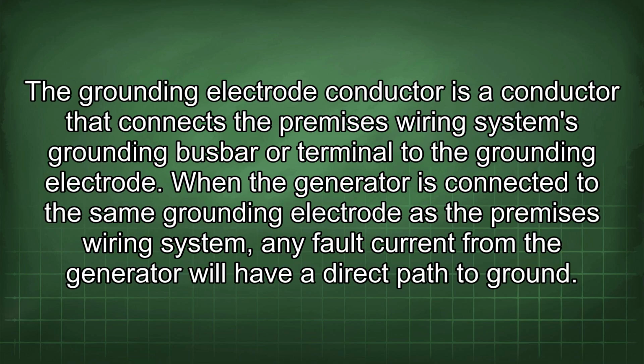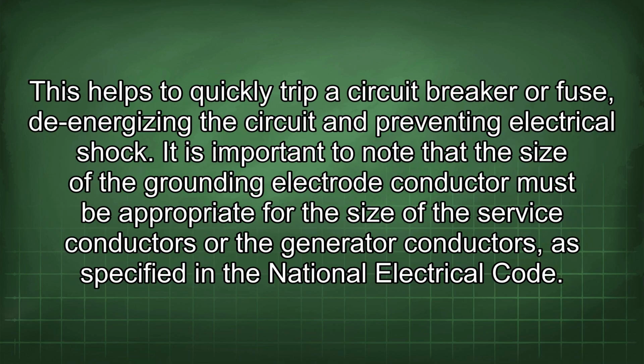The grounding electrode conductor is a conductor that connects the premises wiring system's grounding busbar or terminal to the grounding electrode. When the generator is connected to the same grounding electrode as the premises wiring system, any fault current from the generator will have a direct path to ground. This helps to quickly trip a circuit breaker or fuse, de-energizing the circuit and preventing electrical shock.